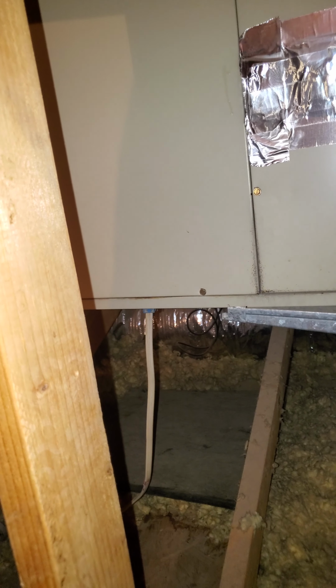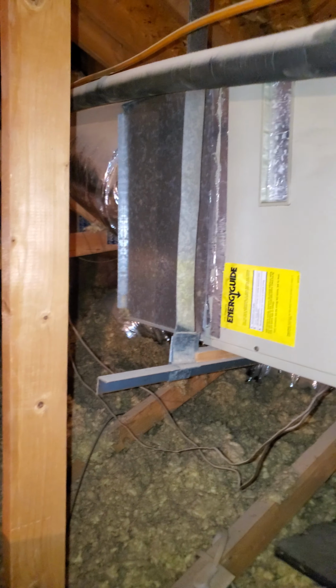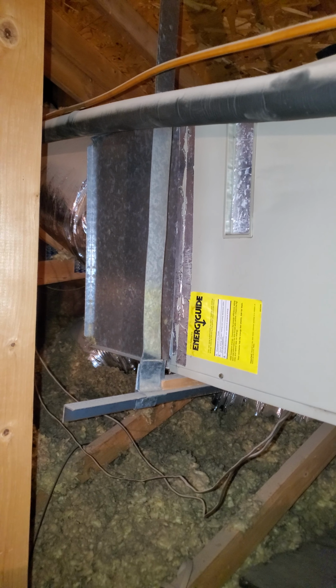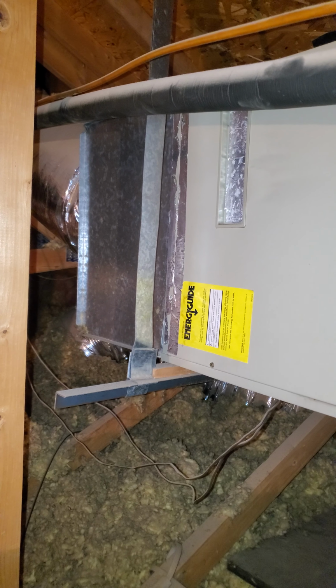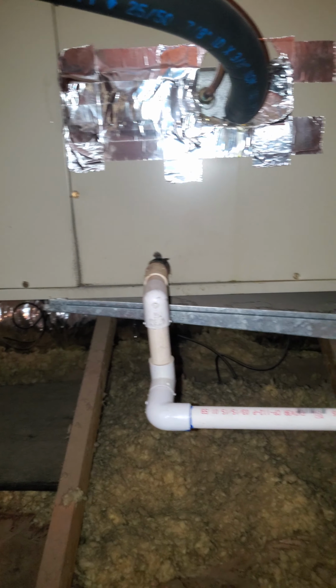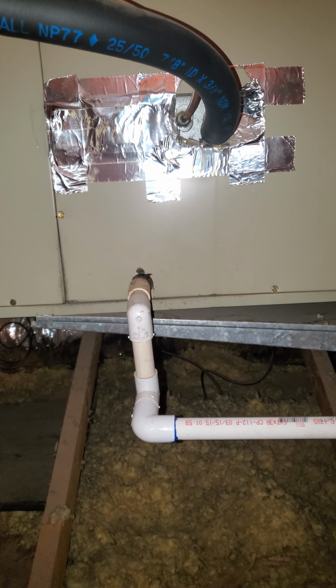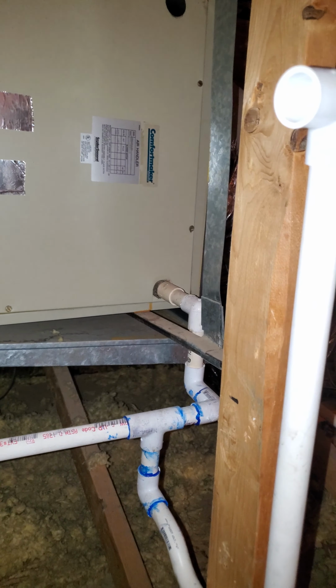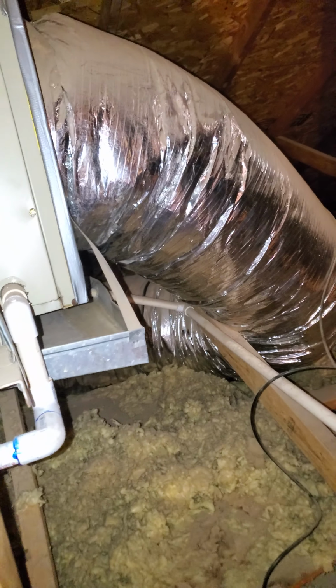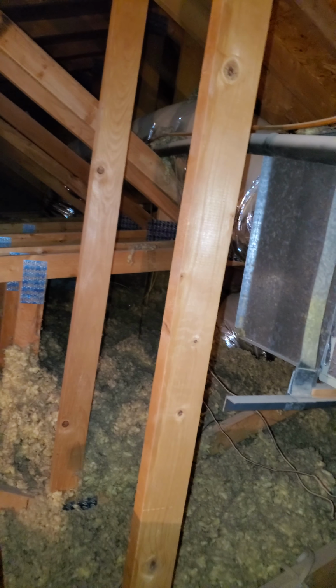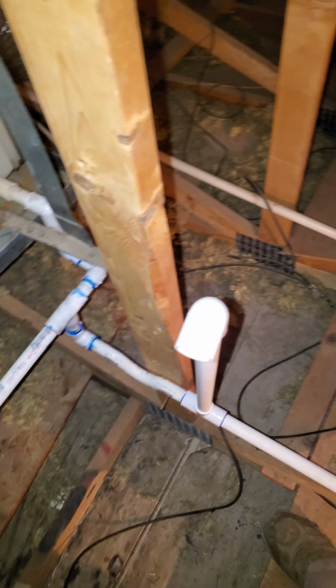So we're going to do it right. We're going to re-level it with new supports. We're going to put the right size drain pan on that covers the entire air handler, the entire length and width of it. We're going to put the right ductwork on the back end and the front end. And then of course, we're going to redo the plumbing here, clean it out.